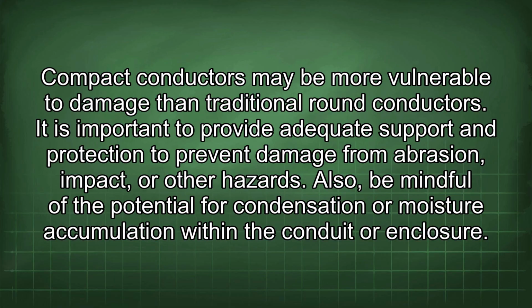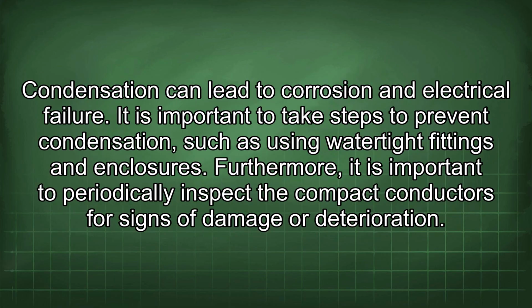Also, be mindful of the potential for condensation or moisture accumulation within the conduit or enclosure. Condensation can lead to corrosion and electrical failure. It is important to take steps to prevent condensation, such as using watertight fittings and enclosures.